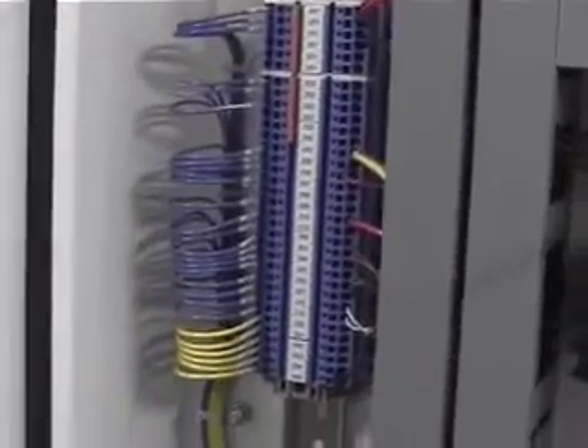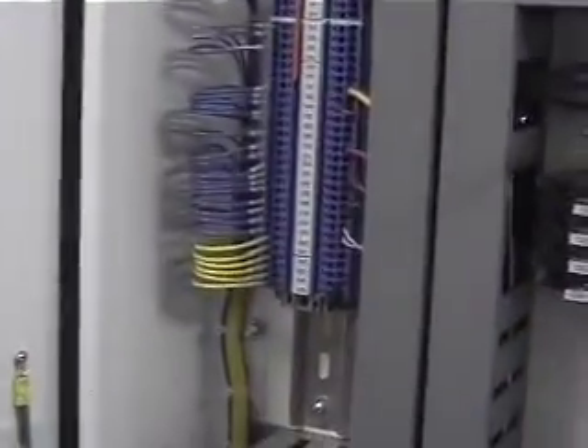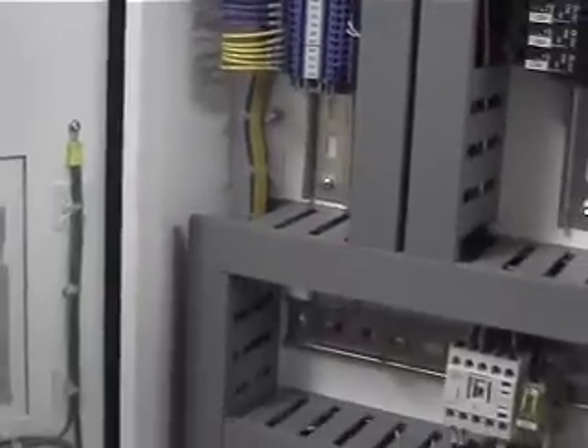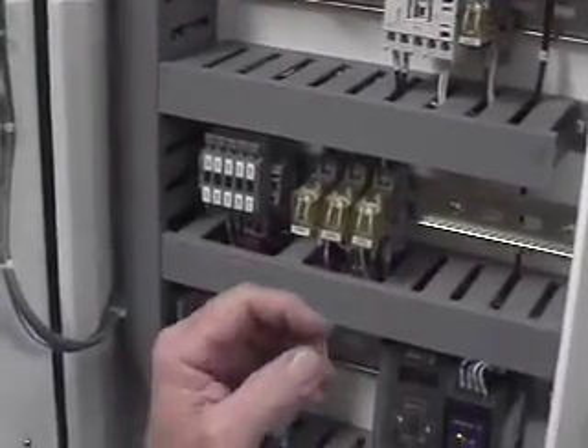In this case, 501 is CR1, and 502 and 503 is CR2. Those are your two alarm outputs. So to your point, if you wanted to bring a BMS system in here, you'd come in and connect to those two. They are single pole double throw relays.